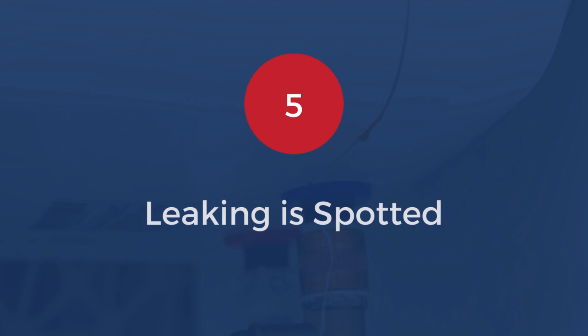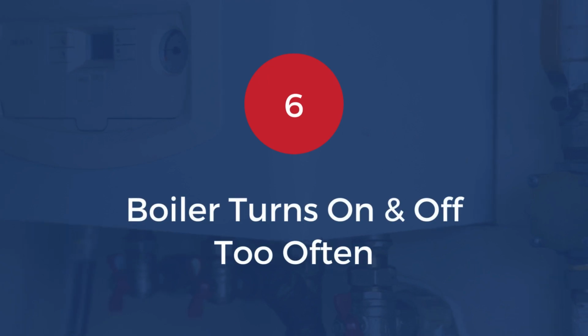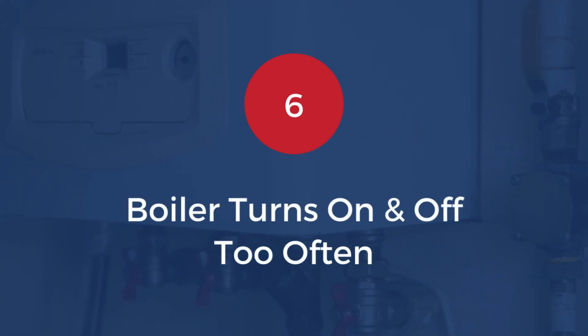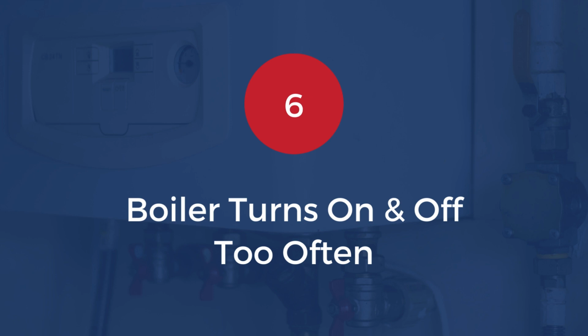6. Boiler turns on and off too often. A boiler that cycles on and off too frequently might be affected by low water pressure, or by a faulty thermostat. If a valve that should be opened was somehow closed, that could cause rapid cycling as well. You can check all the valves yourself to make sure they're open. It's also a good idea to call your local water company to see if other customers are experiencing low water pressure, meaning the source of the trouble is outside your home. Otherwise, a boiler that keeps turning off unexpectedly should be examined by a professional.